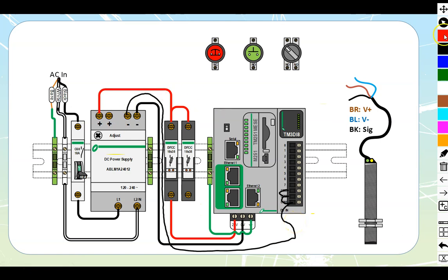The next thing we would do is we would take our positive around. So you don't want to take it directly from the power supply. You do want to take it out of a fuse holder itself to protect that circuit because you're running out to field devices. So you could drop in onto each of your individual field devices. We're just running a hot stinger all the way around. At this point, we have got our field devices powered up.